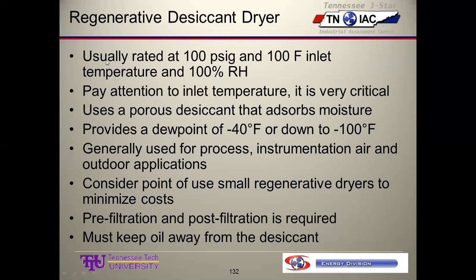Again, on these ratings, we say that these are rated for 100 PSIG, 100 inlet, and 100% relative humidity. Pay attention to inlet temperature. It's very critical in the operation of these. You don't want to go above it. This is coming out of your compressor. You'll affect it. It won't operate as well.